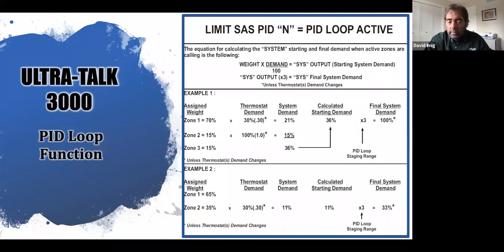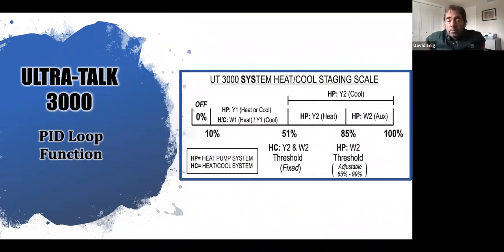Down below in zone 2, very simply, example 2 is a 2-zone system. It's calling in zone 2, it's calling 30%, which means I have a communicating thermostat in zone 1 and 2 here. 1 is not calling, 2 is giving me 30% times my 35, which is the weight I gave it in this example, gives me a starting system demand at 11. 11 times 3 gives me 33%, which means I can go no higher than 33% to satisfy that call. Why is that relevant? I'll show you here. This hopefully makes more sense.